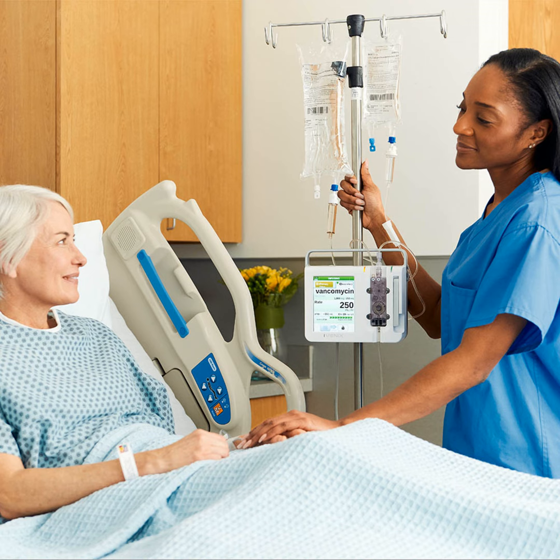If the pump has a locking feature, remember that touch screen, once you unlock it, your PIN is paired with your care profile. And remember that care profile is either your critical care or med surg. So once you unlock it, you're already in the right care profile. Remember, you're taking away all those steps for the nurse with this type of capability, and you're actually removing the potential of an incorrect selection. So again, just making it easy from an automation perspective. In line with automation, nurses should not be spending time on the mechanics of setting up an infusion. We are often seen as the bridge or that shock absorber between the device and the patient. And actually, we should just throw that away. The pump should just work.